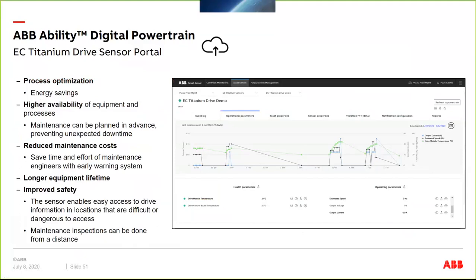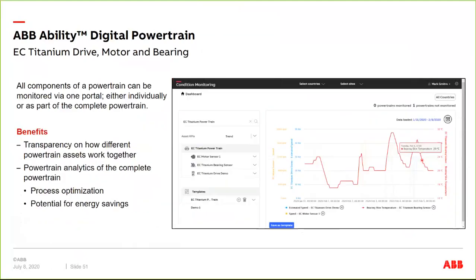Obviously it's a predictive and preventative maintenance tool designed around reducing maintenance cost, because unexpected downtime is far more expensive than doing preventative maintenance. So the idea here is to get a window into equipment so that you can do preventative maintenance ahead of any type of catastrophic failure. So you can look at the web portal and look at the drive parameters specifically that it's monitoring, but they're all digitally time-stamped. So you can also go in and look at them on what's called the digital powertrain.